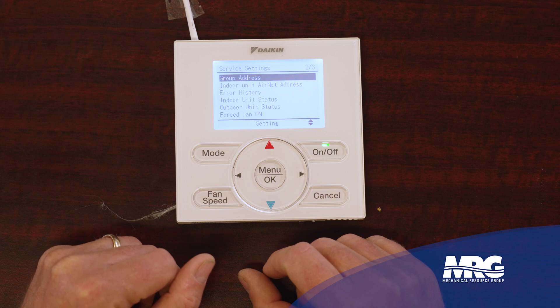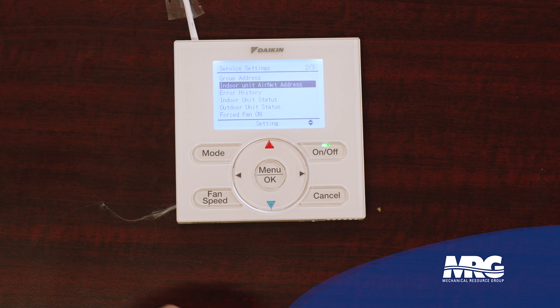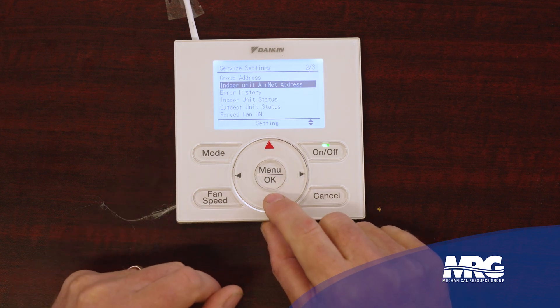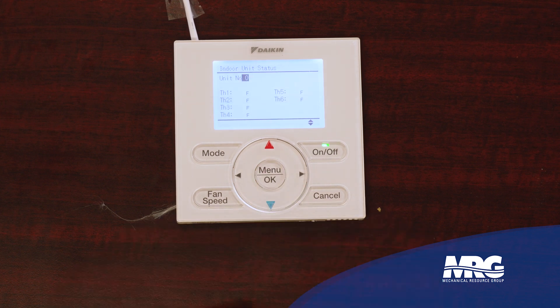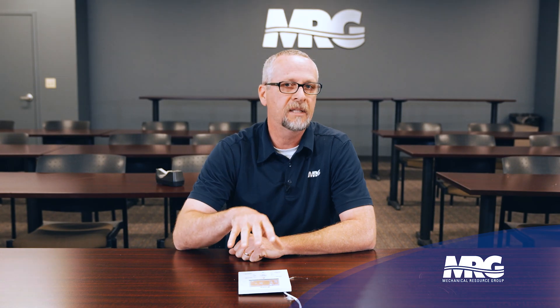Not only can we lock the stat out, we can lock out specific buttons — you have to get into the service settings to do that. Set point differentials, group addressing — a very big one at startup. Group addressing, indoor AirNet addressing, and field settings are the major things we use when starting this gear up. But here's another really cool one: thermistor values. I can look at my superheat on my indoor unit because I have an expansion valve in my indoor unit. I can see my return air temperature is 74, my gas pipe temp 51, and my liquid pipe 45. I've got about a 6-degree superheat — that's pretty good on a VRV system. Not all indoor units will have this; it depends on the vintage and equipment type.